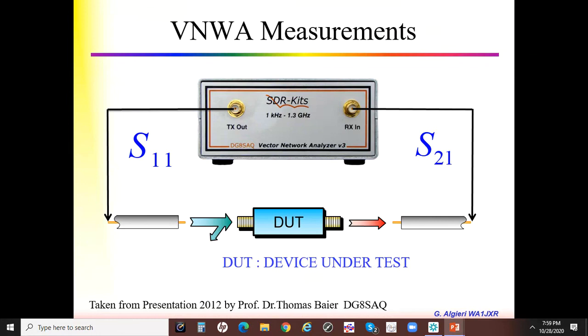So the basic way that we would use this vector network analyzer is we would take our device and we would connect it up to the ports of the analyzer. If we had a 2-port device, then we would connect it up as such, one port to the TX out and the other port to the RX in. If we were measuring a single port device like an antenna, we would just connect the antenna up to the TX out and leave the RX in port open. If we were measuring a coax transmission line or a filter or something, then we would connect it up to the 2 ports.